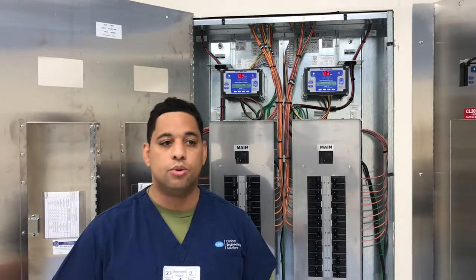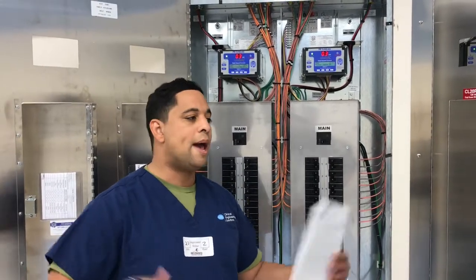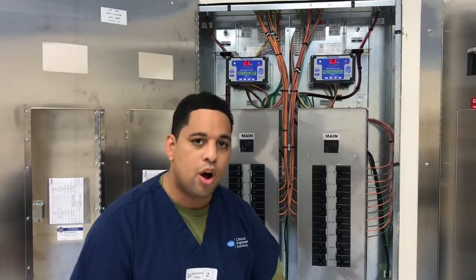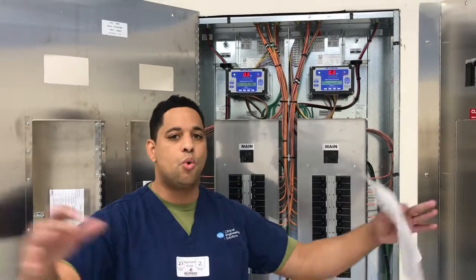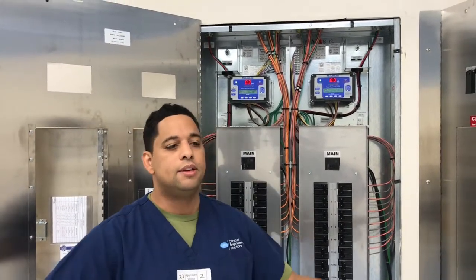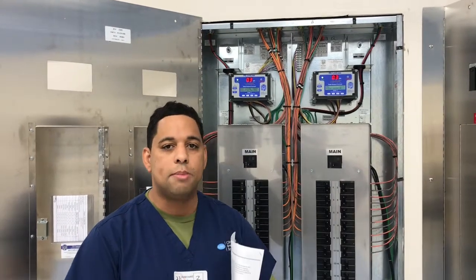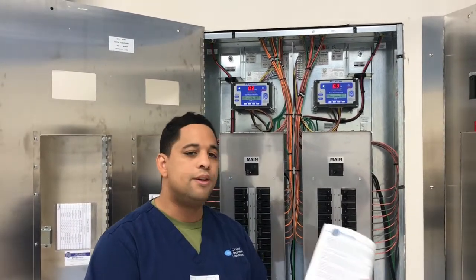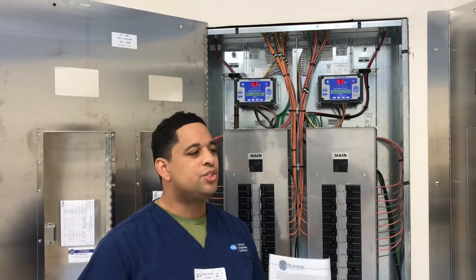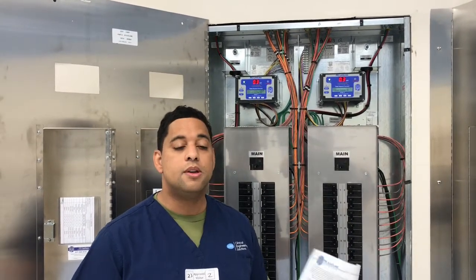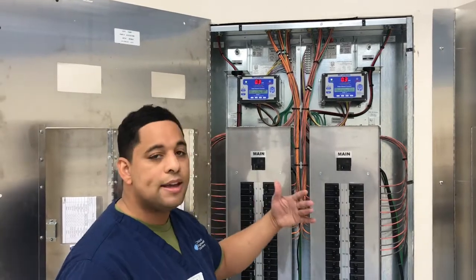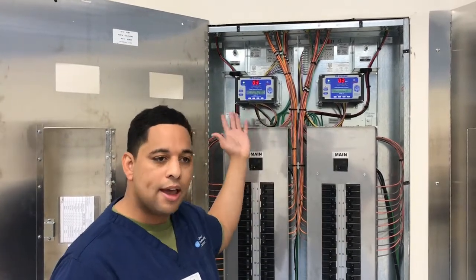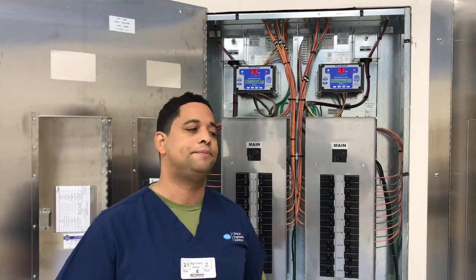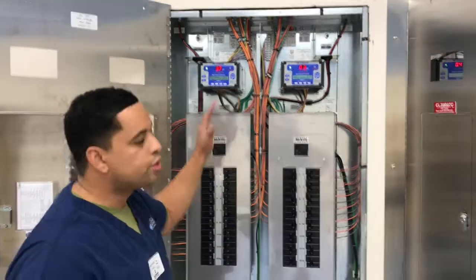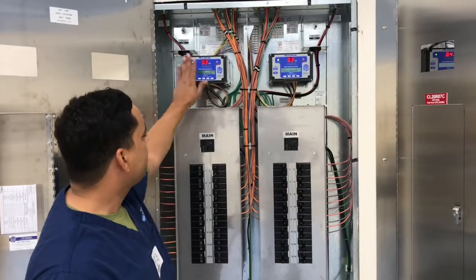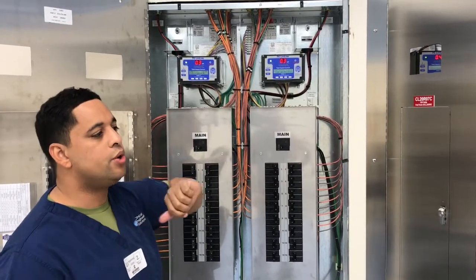Example number 2. You're working in the room and someone knocks over a bag of saline, and now it's poured all over the medical device. There's water in it, saline in it, and water and electricity don't mix very well, so the device is going to malfunction. Just 2 examples. There are many others, but those are some ways in which a device will malfunction and cause high leakage that needs to be fixed.